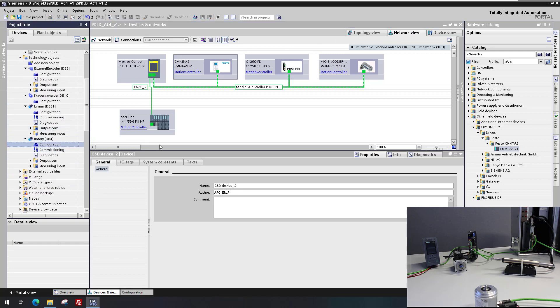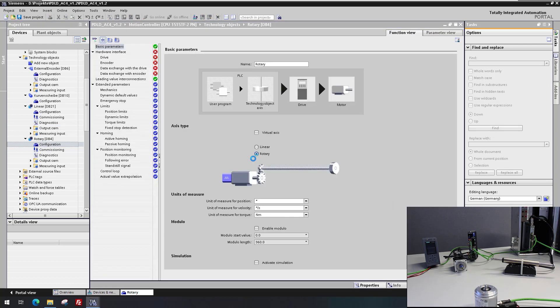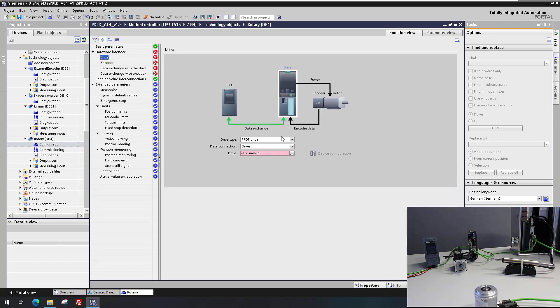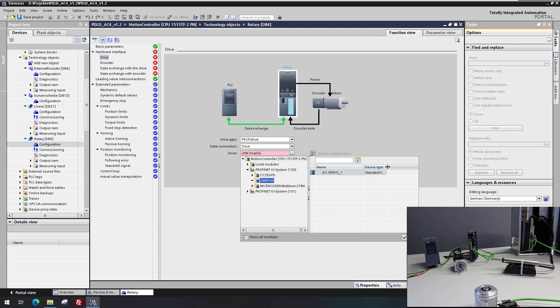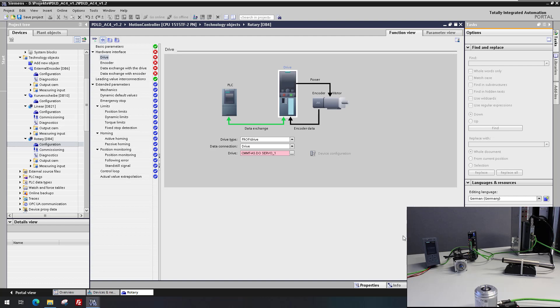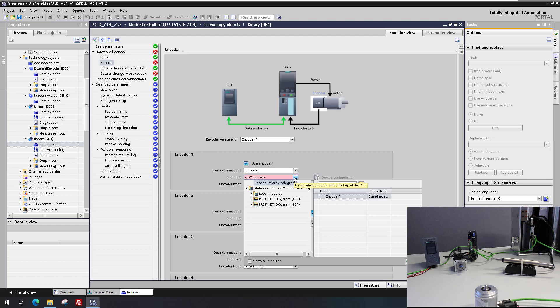The second step is the interconnection at the technology object. In the hardware interface configuration of the drive, the configured telegram is selected. Additionally, for position control, the telegram data from the drive encoder must be interconnected at the hardware interface.